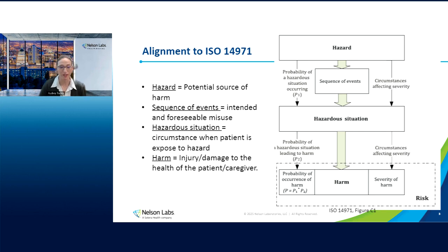It's really hard to talk about these topics in silos, so I'm going to weave them throughout the presentation today so you can hear how I will be applying these in our risk assessments. So when I look at a hazard, again, that's the potential source of harm. Then we have to have a sequence of events in order for a hazardous situation to occur. And that really stems from exposure. So we think about foreseeable misuse, we think about bioaccumulation, we also think about intended use of the product. And that will lead us to determine if harm is possible, and then what is the severity of that harm, so that we can then calculate risk.